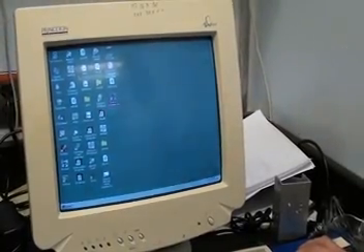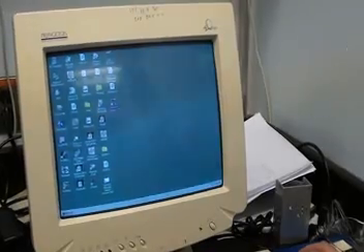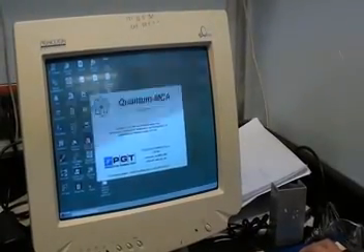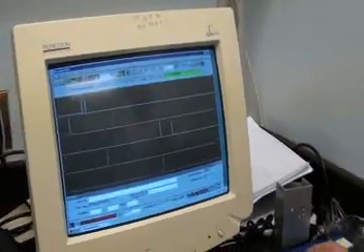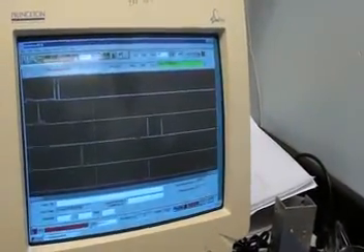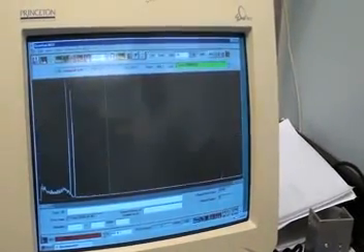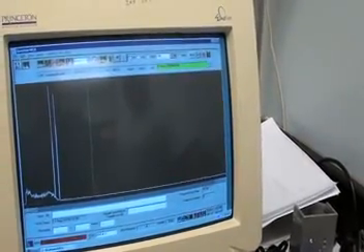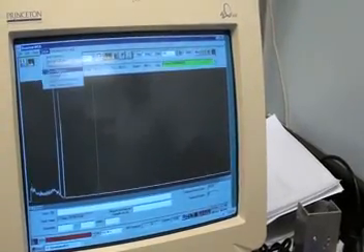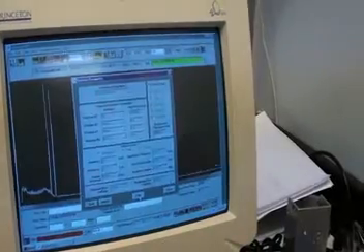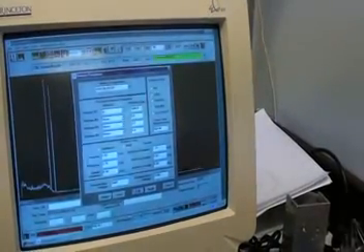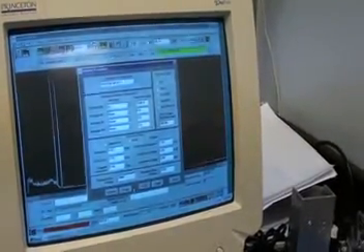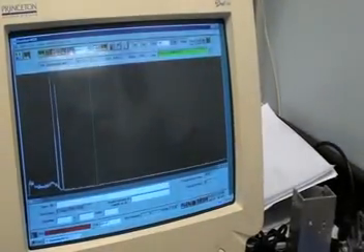Go over to the Quantum — whichever one you have, MCA Gold. Double-click on the icon and it should bring up the Quantum. It gives you various lines there to look at. First we are just looking at one main line. Once we get this set up, look over at the detector parameters. You can set the bias for your detector, pick out what type of crystal you have — P-type or N-type. You can load all this information, save it, apply it, and close — and you are ready to go.